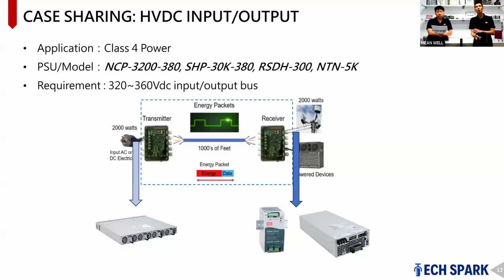For example, if you want to bring the wire from one building to another, or from the bottom of the building to the top, in the US you usually have to use conduit because of the voltage hazards. With this Class 4 system, you can put a transmitter at one end and a receiver at the other, using just regular 18 gauge wire, no conduit needed. That saves a lot of cost for the building, and you don't even need a certified technician to do the installation.